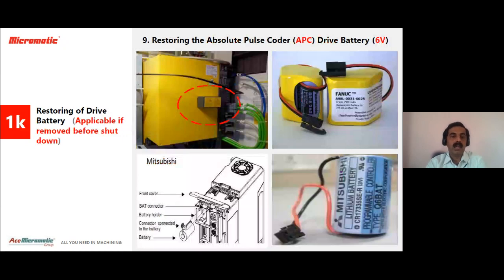Now again, there is a battery called drive battery, as you know. This is also applicable to restore if it is removed before the shutdown. So now what we have to do is restore this absolute pulse coder, that is called APC. The drive battery voltage must be 6 volt. See, if the voltage is low, then it will show an alarm in front of the screen. That means the battery is getting drained. So we have to re-establish this battery as shown on the left side in the circle.